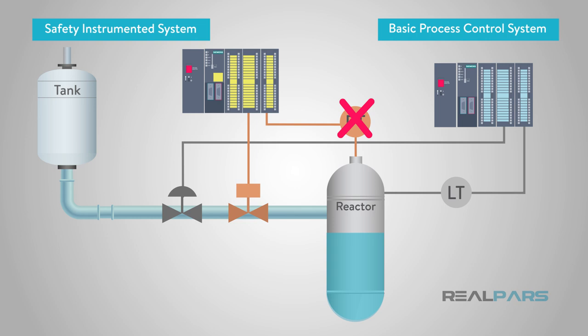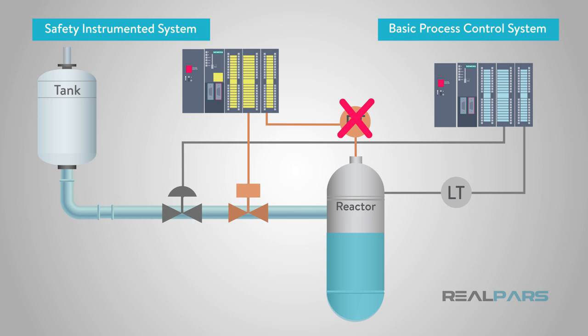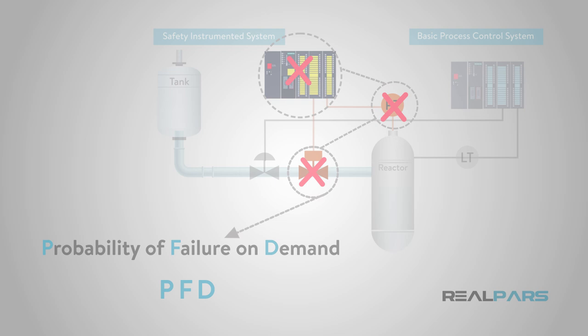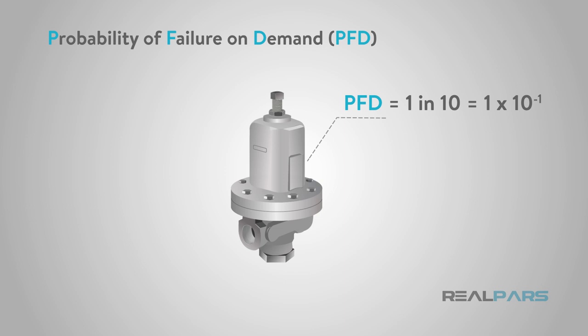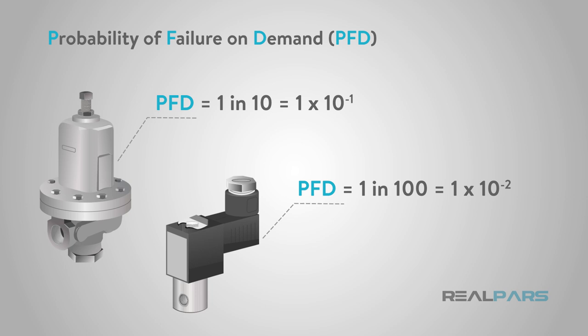Even a safety instrumented system has a probability to fail. What if the pressure sensor does not detect the high pressure condition? What if the isolation valve does not close when it is told to? The probability that a device — whether input, output, or logic solver — will fail, causing the SIF to not respond when called upon, is called the Probability of Failure on Demand, or PFD. For instance, a pressure regulator has approximately a 1 in 10, or 1×10⁻¹, probability of failure in a year's time. Failure of an isolation valve is about 1 in 100, or 1×10⁻². These values can be obtained from vendor data or from industry databases of typical PFDs for each type of device.